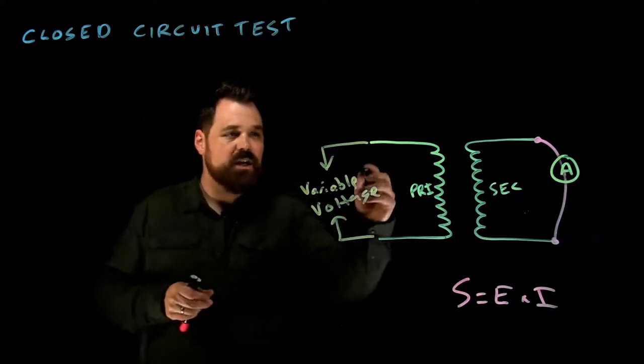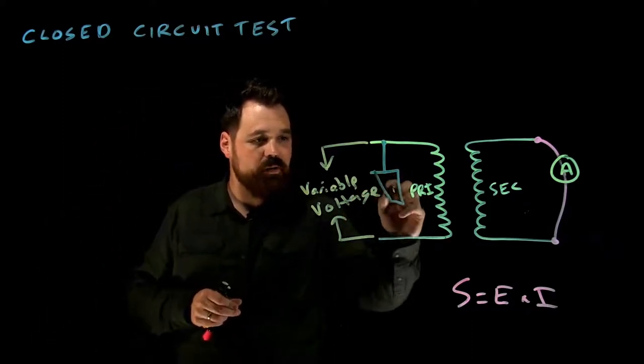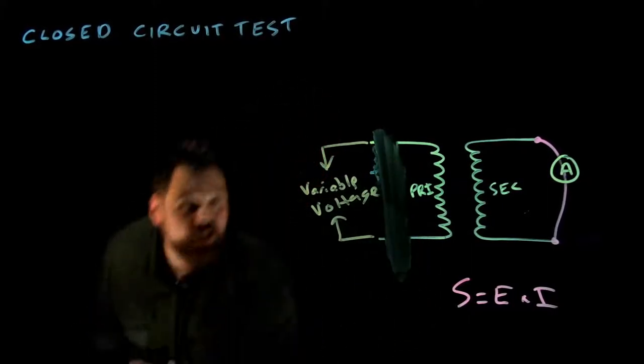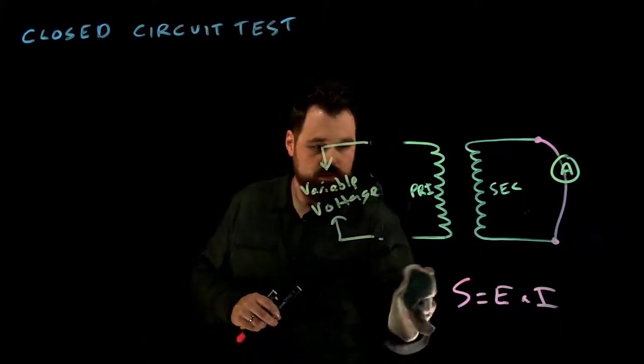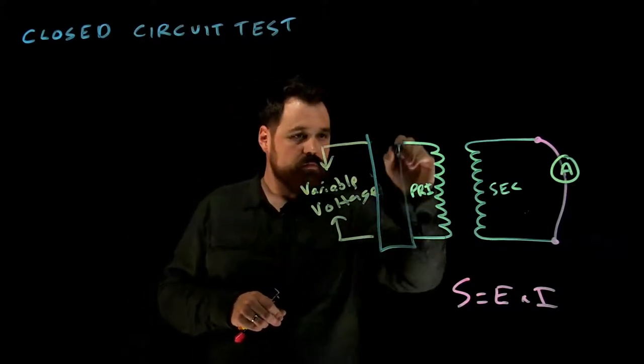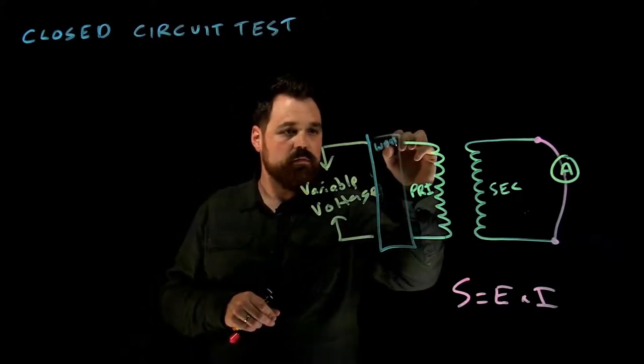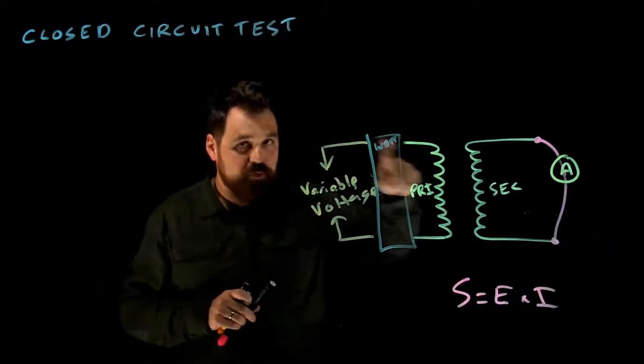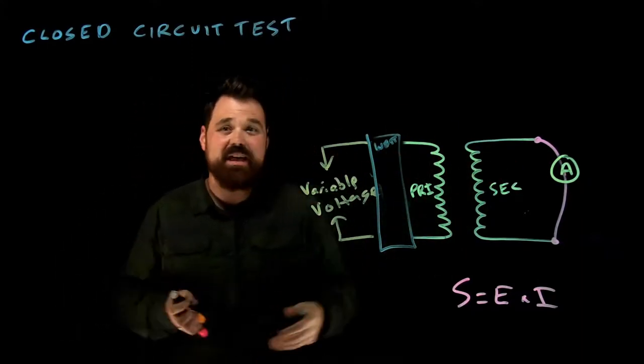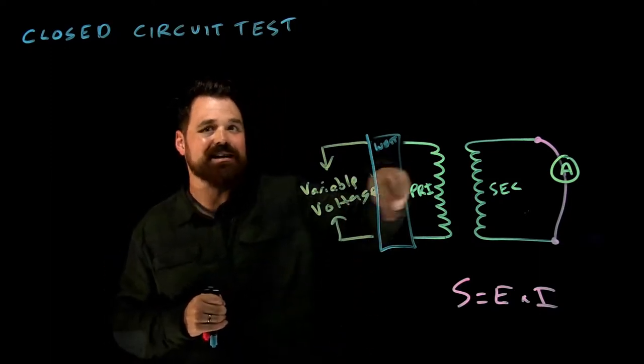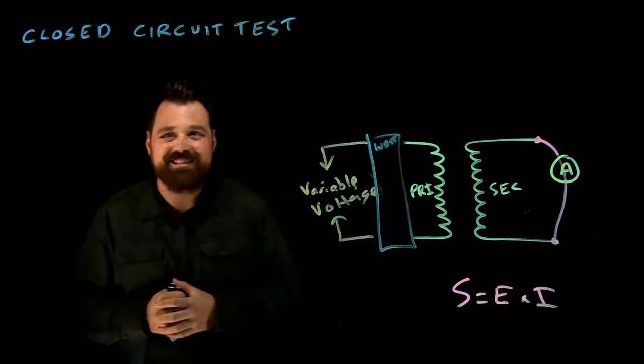Now, one other benefit is if I put a wattmeter here - the wiring would be a little bit different. Let's take a quick look. If I were to put a wattmeter in the circuit, I'm able to get that primary current to flow as well as the secondary. And that'll allow me to measure my losses, or my copper losses of the transformer, because I'll get that high current flowing and the secondary current flowing.